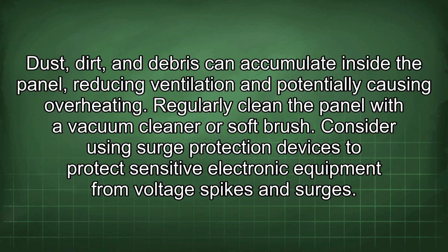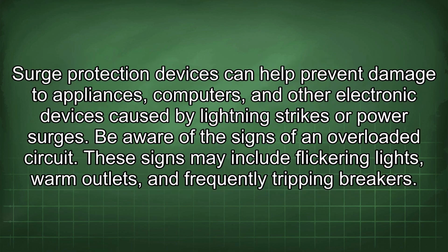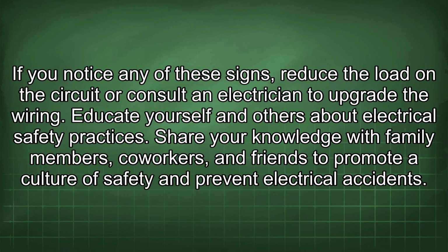Consider using surge protection devices to protect sensitive electronic equipment from voltage spikes and surges. Surge protection devices can help prevent damage to appliances, computers, and other electronic devices caused by lightning strikes or power surges. Be aware of the signs of an overloaded circuit. These signs may include flickering lights, warm outlets, and frequently tripping breakers. If you notice any of these signs, reduce the load in the circuit or consult an electrician to upgrade the wiring.